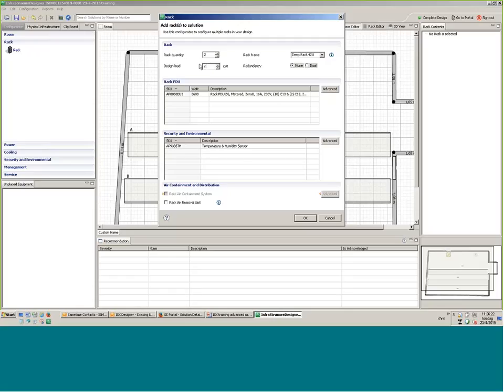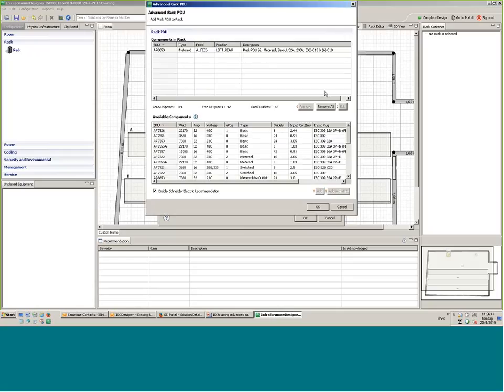So if I go to 7 here, you will see it's now a 32 single phase, and it's recommended to have 3 temperature sensors. If I change to dual, I will get 2 UPS. So if you have N+1, which 90% has, you can go to advanced and put the same rack mount PDU again if you want, or change it totally.